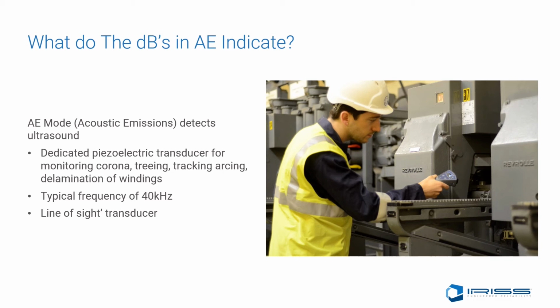Using an airborne structure-borne ultrasound sensor on the exterior of the item under examination, internal partial discharge can be detected and located with the sensor if it's placed closest to the source. If you add the VPDS from IRISS, you can actually get a reliable test point with one single location instead of having to trace the seams. This will give you a repeatable test point for the detection of ultrasonic emissions and TEV occurrence inside the electrical gear.